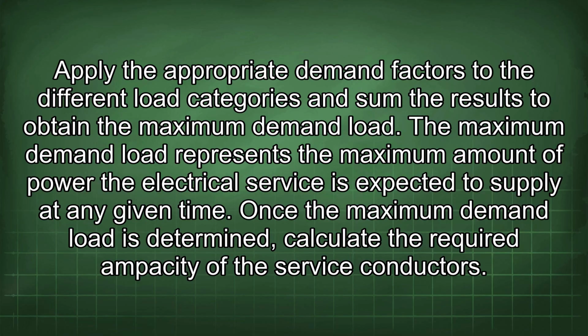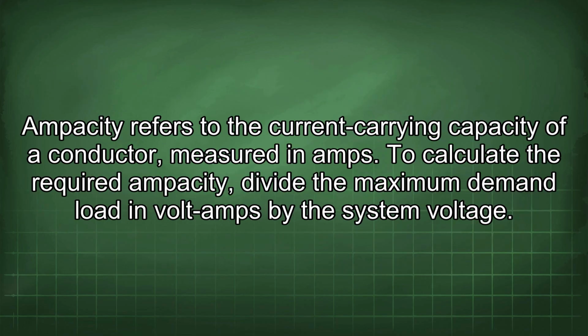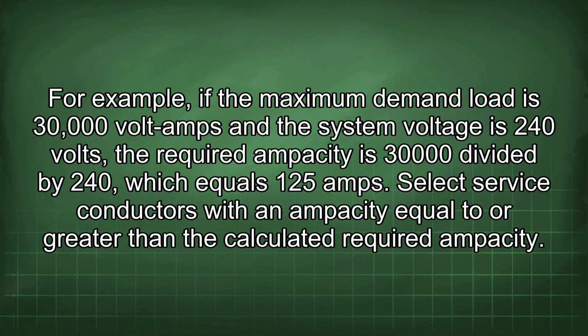The maximum demand load represents the maximum amount of power the electrical service is expected to supply at any given time. Once the maximum demand load is determined, calculate the required ampacity of the service conductors. Ampacity refers to the current carrying capacity of a conductor, measured in amps. To calculate the required ampacity, divide the maximum demand load in volt amps by the system voltage. For example, if the maximum demand load is 30,000 volt amps and the system voltage is 240 volts, the required ampacity is 30,000 divided by 240, which equals 125 amps.